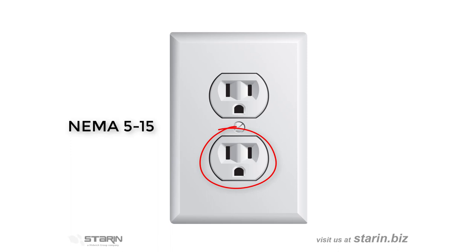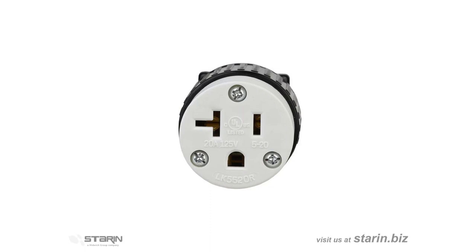Occasionally we use devices that draw 20 amps. Typically these devices have a plug with one vertical prong for live and one horizontal prong for neutral, along with the peg for earth ground. These are called NEMA 5-20. While there are a lot of wall receptacles that have a T-shaped neutral that can take both 15 and 20 amp plugs, you'll need to make sure that the EC installs a suitable receptacle for a 20 amp plug.